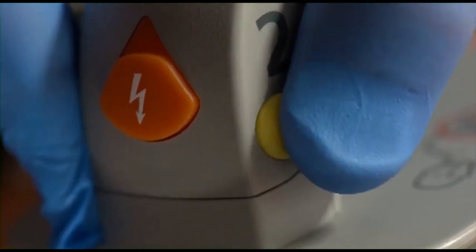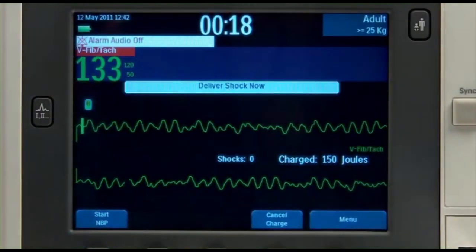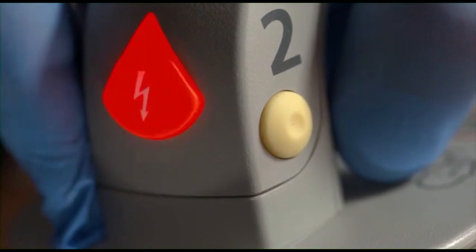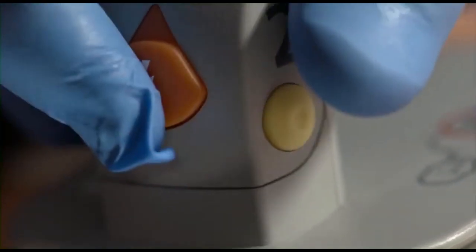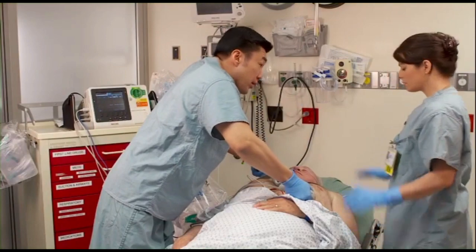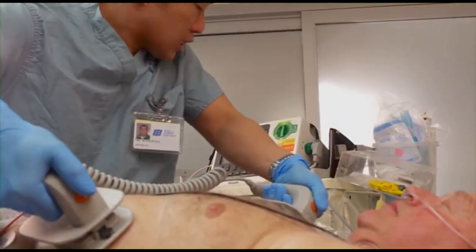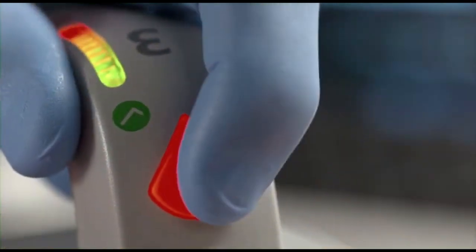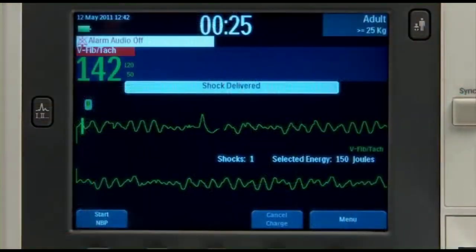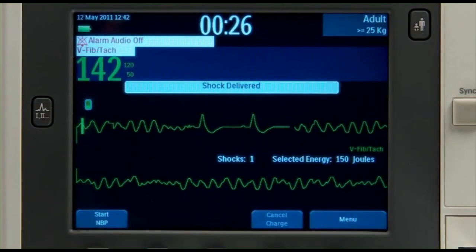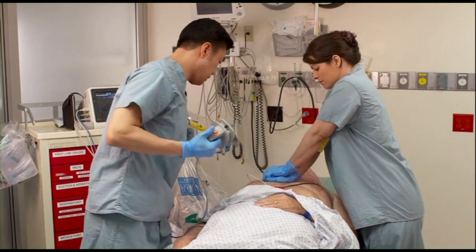During transthoracic defibrillation, the energy stored in the capacitor is delivered at a relatively rapid rate to the chest of the subject. For effective defibrillation, it is advantageous to adopt some shaping of the discharge current pulse. The simplest arrangement involves the discharge of capacitor energy through the patient's own resistance.